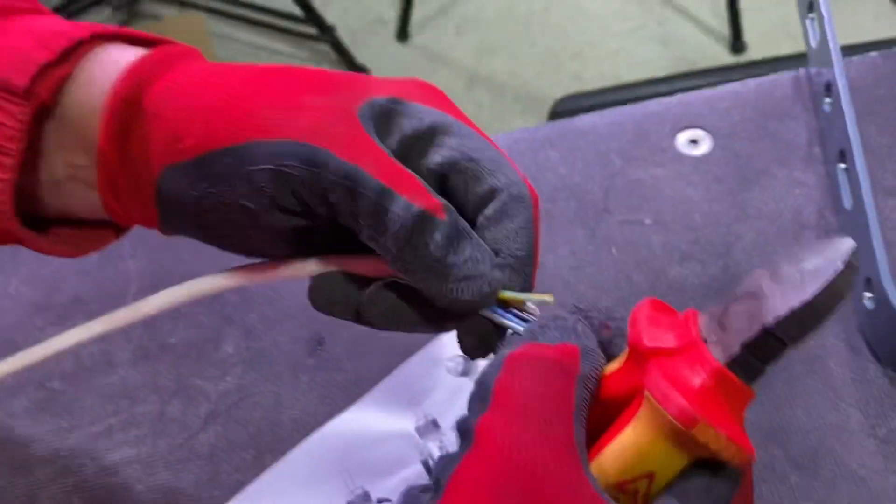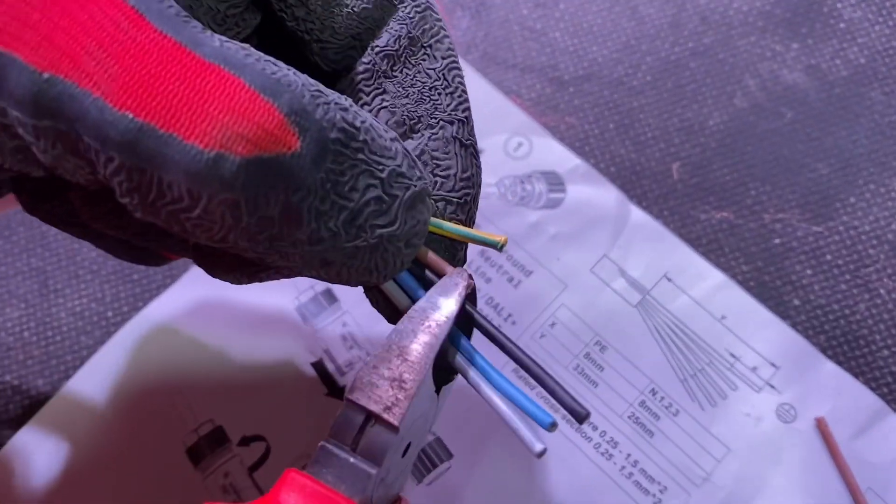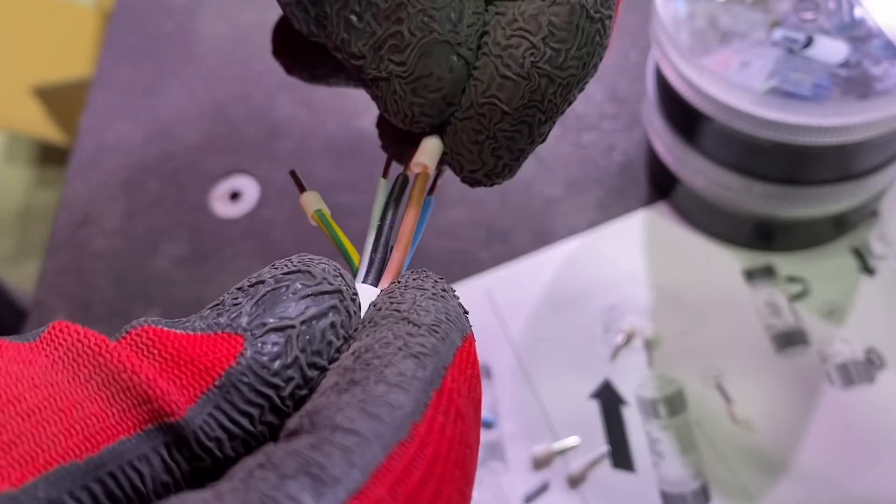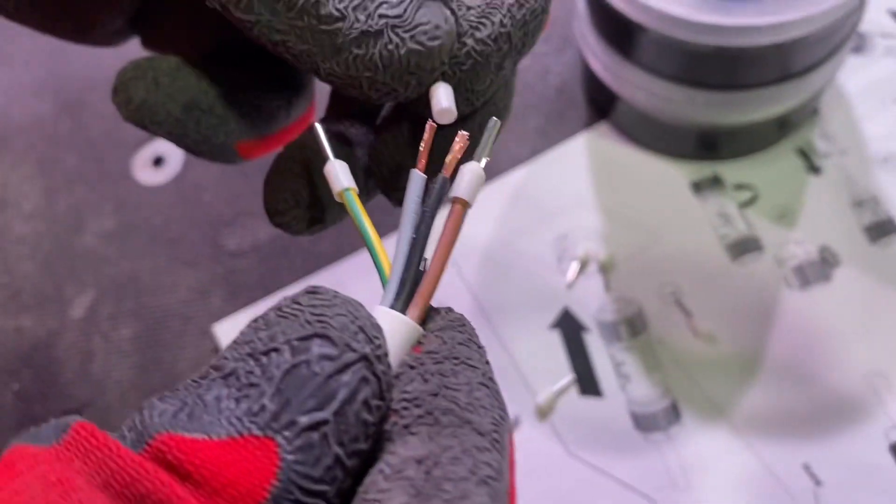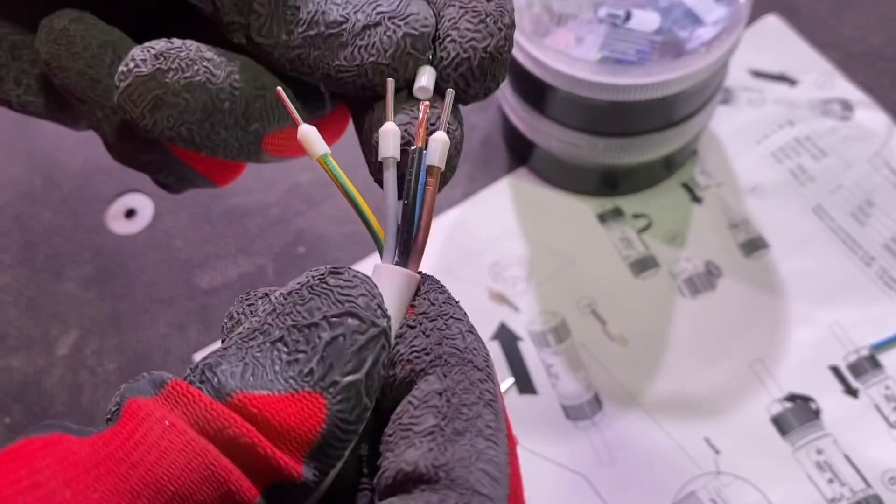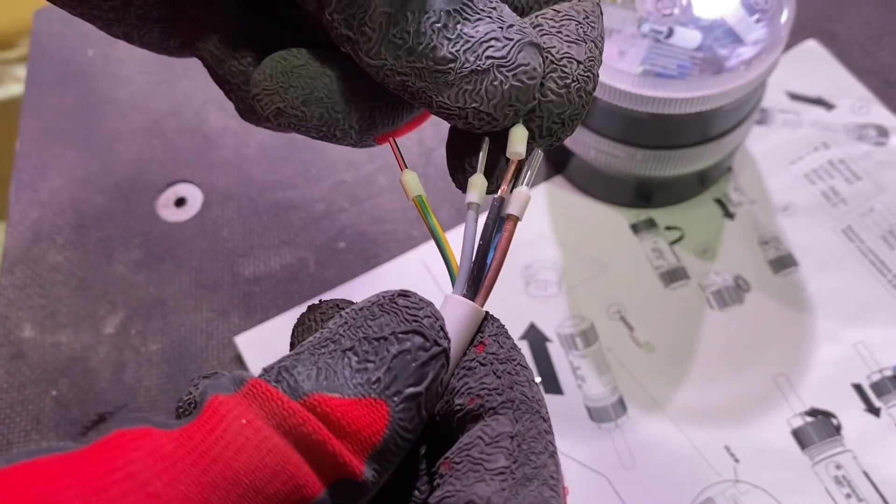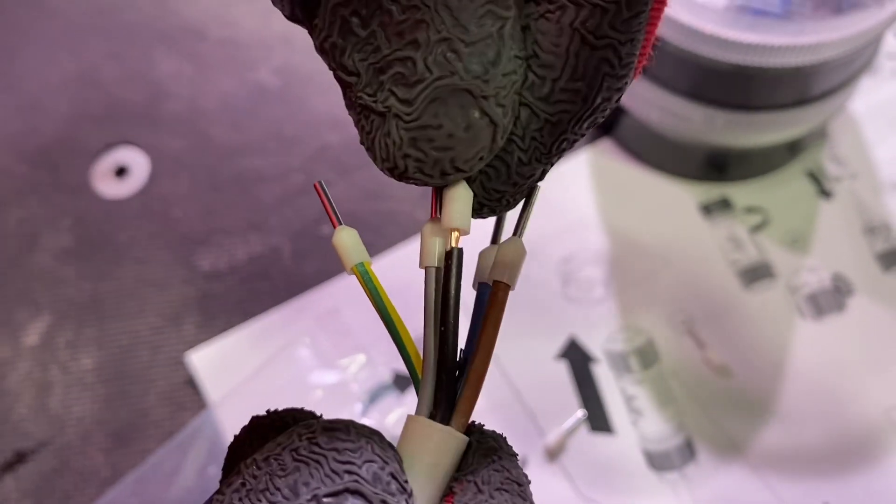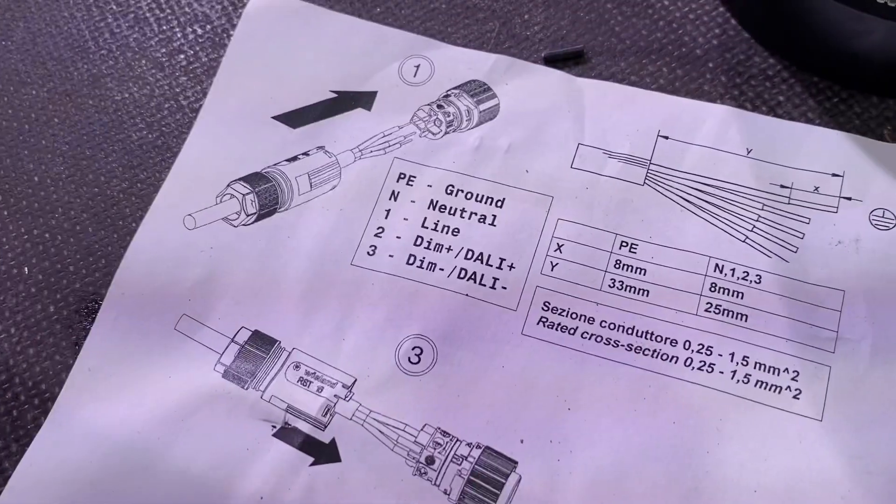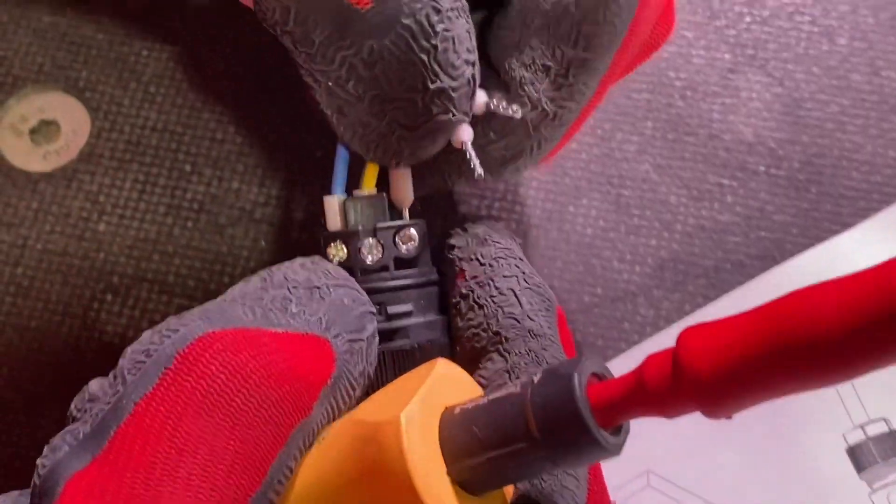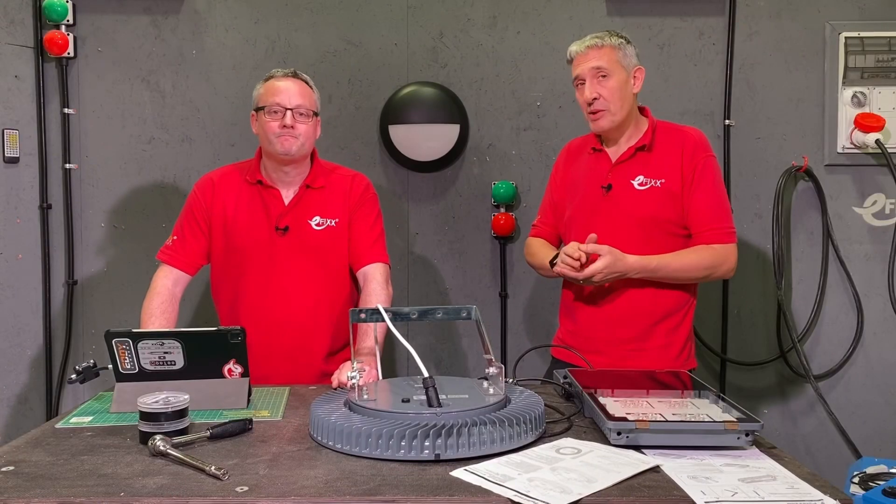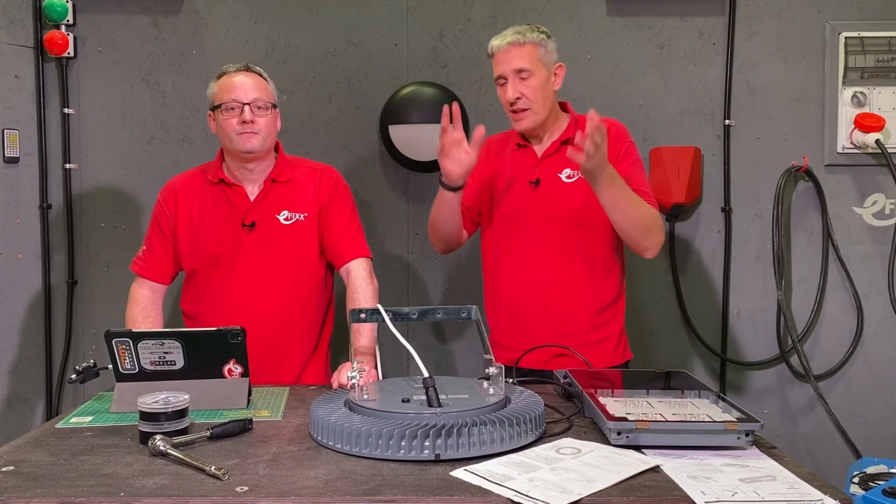So other options, we can have these in emergency versions as well. We can also have them in the one that we're going to cover soon on the channel. We can have it in Dali as well. We've been asked and requested it and we can do a Dali connection as well. And that comes down to connections, Gary. I knew you'd get back to the connections. Is that safe territory for you? It is safe territory for me. But of course, with the minute we mentioned connections, I noticed the ferrules are out and you're making those connections into this adapter here in order that we can make that connection. So, of course, we love a ferrulled end. There's more connections now because we've got the Dali. Just talk me through those connections. So the Dali has an additional two connections, a plus and minus for the Dali bus.